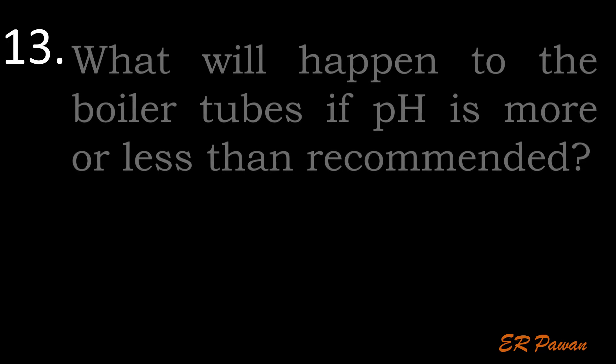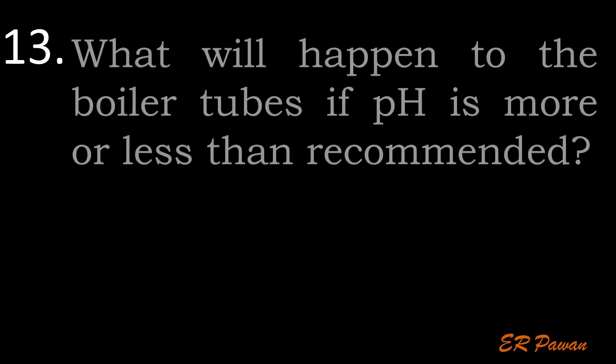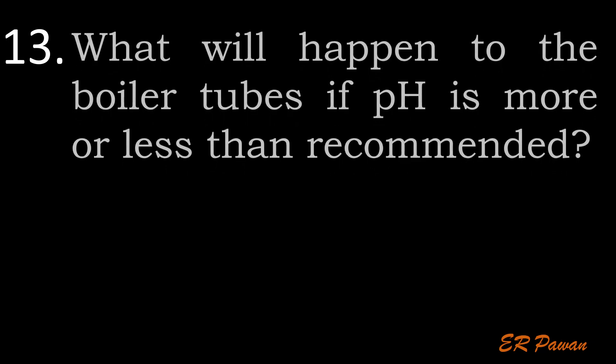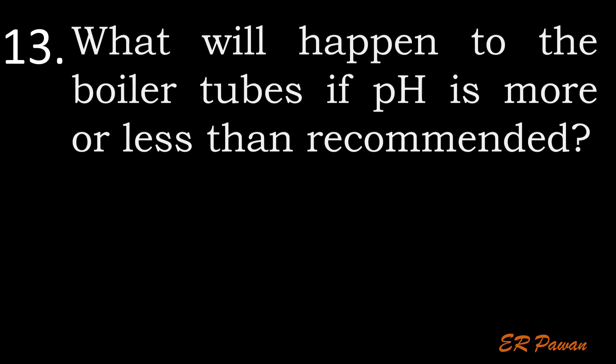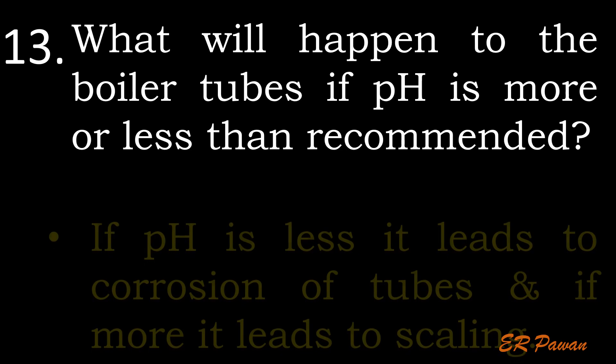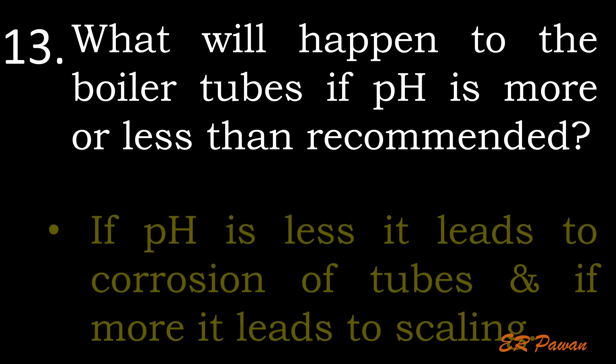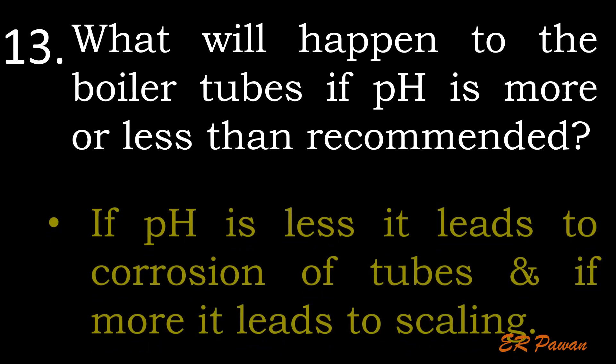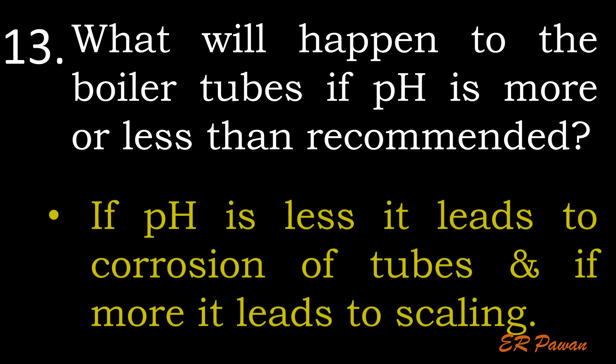Question 13: What will happen to the boiler tubes if pH is more or less than recommended? If pH is less, it leads to corrosion of tubes, and if more, it leads to scaling.